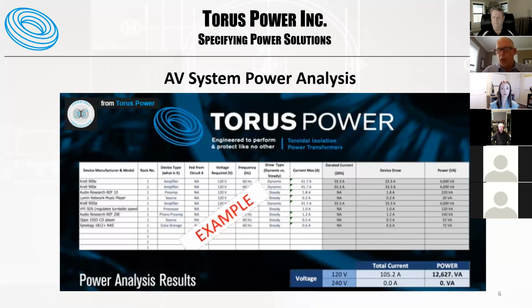Sure, absolutely Mark. In much of what we do, we use 240 to 120 step down transformers in a lot of our products. There's a number of reasons why you'd want to do that. First is the size or capability of the transformer you can use. Once you go from 120 to 240, you've got a lot more power capability to use a larger transformer. At 120 volts you're maxed out at a 20 amp transformer, and a number of systems will require much more than that. So you've got a higher capability available to use in a larger transformer.